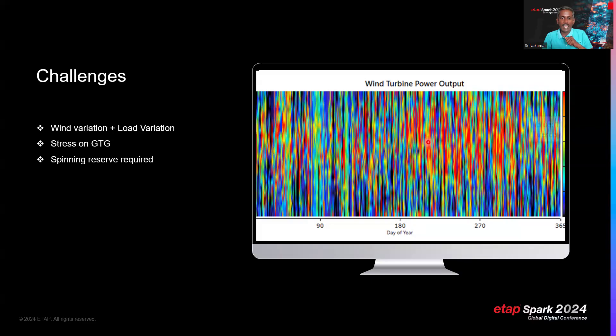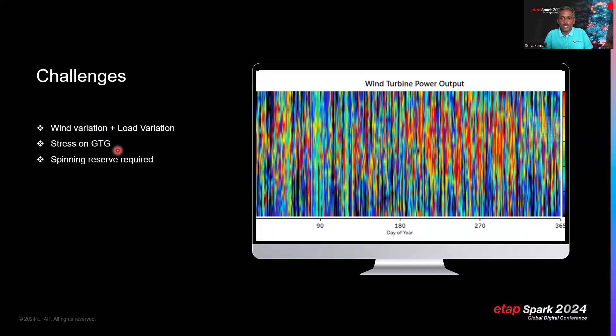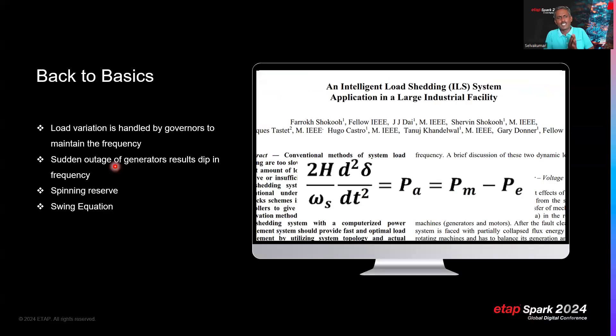With intermittent wind, the governor must regulate frequency not only for load variation but also for wind fluctuation, which is extremely high. This increases stress on the gas turbines. When renewables exceed roughly 10% of installed capacity and are intermittent, the stress on generators becomes significant. Battery energy storage systems are therefore needed to smooth the renewable output, reduce stress on the gas turbines, and maintain adequate spinning reserve.